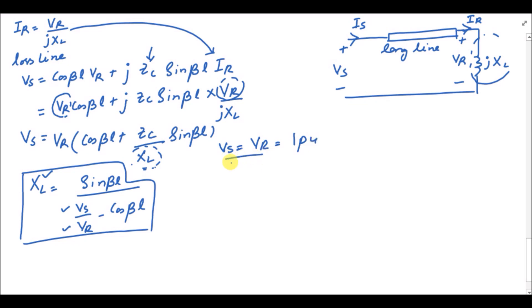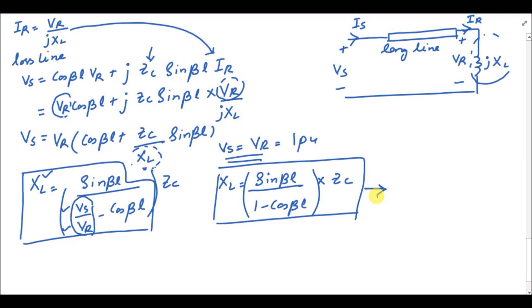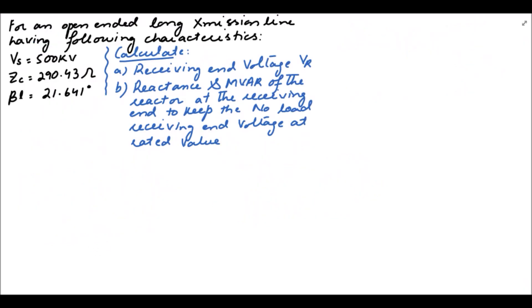If you want to maintain a constant voltage profile throughout the transmission line, you set Vs = Vr, which is commonly 1 per unit. When Vs = Vr, the fraction Vs/Vr becomes equal to 1, so the XL formula simplifies to: XL = Zc·sin(βl) / (1 − cos(βl)). This is the formula to use for a constant voltage profile throughout the line. Now we have an example in which we will calculate the receiving-end voltage, the reactance value, and the MVAR rating of the reactor.